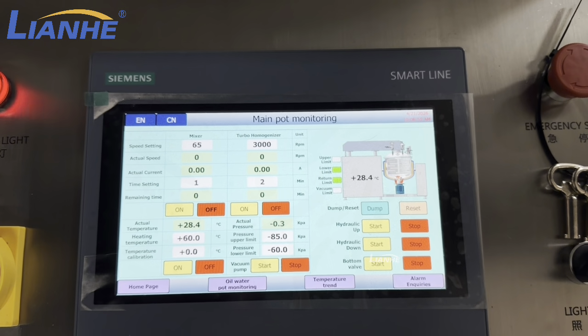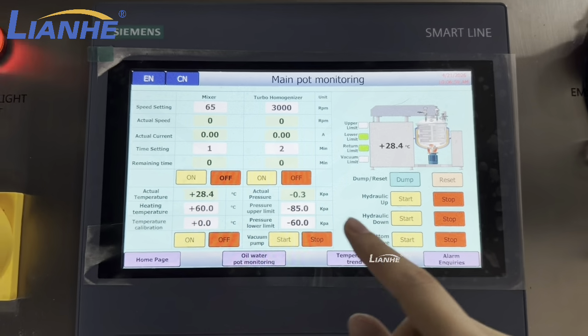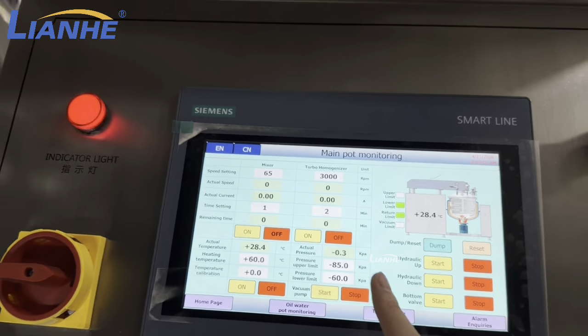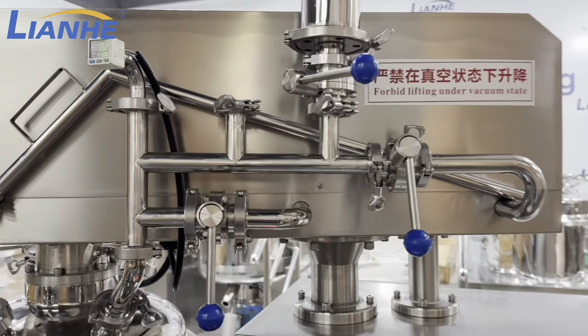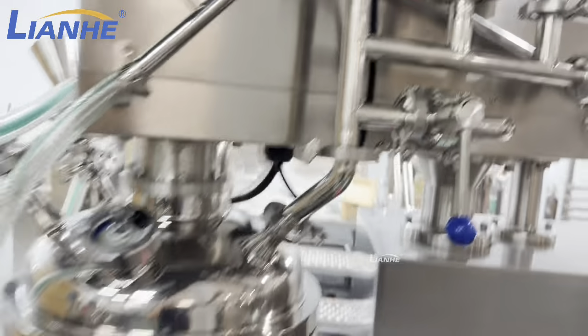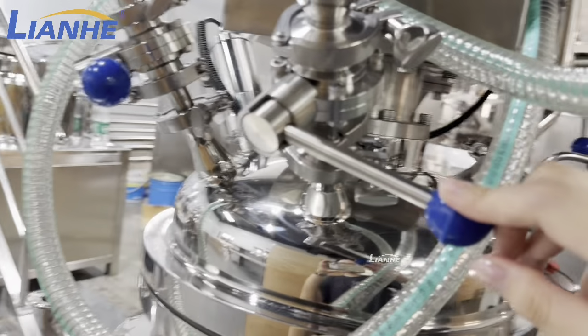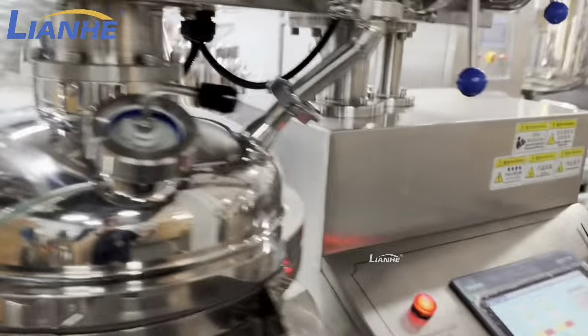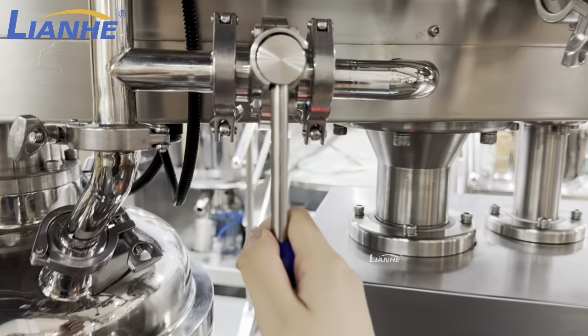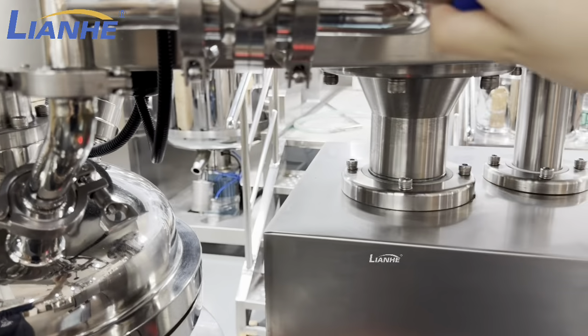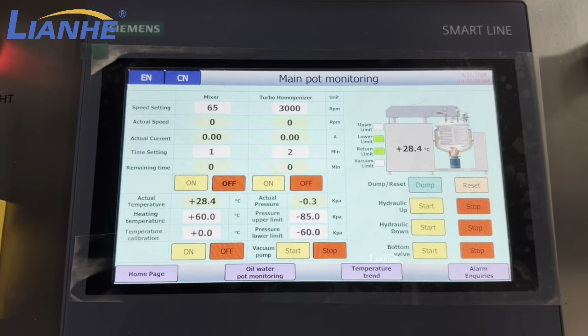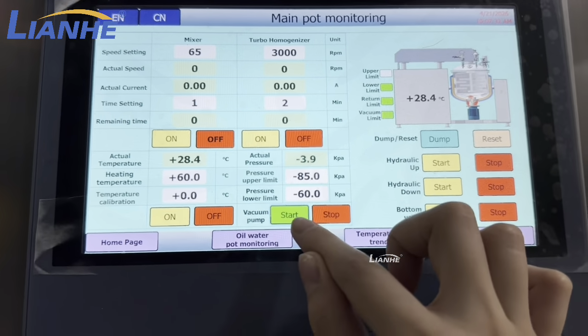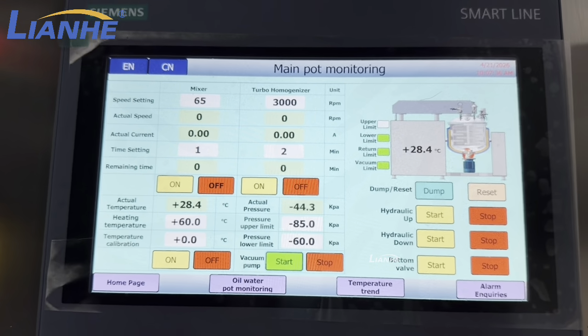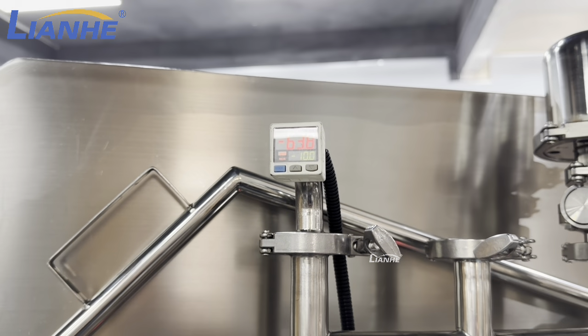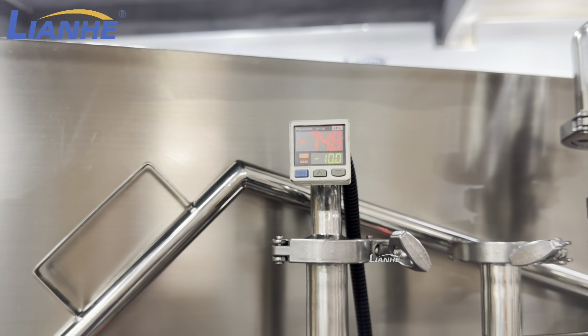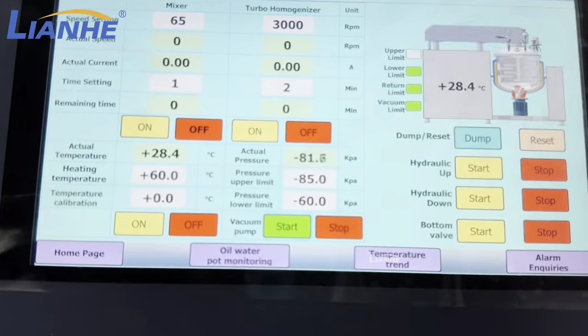Okay, now we can test the vacuum function first. Here we have already set the pressure upper limit and pressure lower limit, and then you should make sure that all the other valves are turned off. This one turn off, and then this one turn off and turn off. And then you can turn on this vacuum pressure valve, and then turn on the vacuum pressure function on it. Now you can see the number is changing. You can check on this vacuum pressure gauge and on the screen.